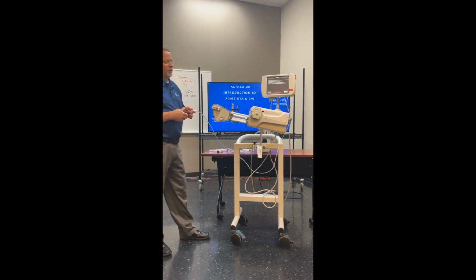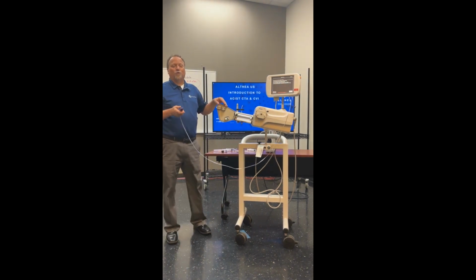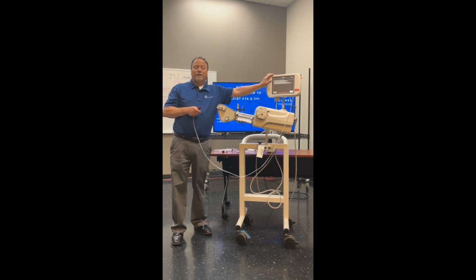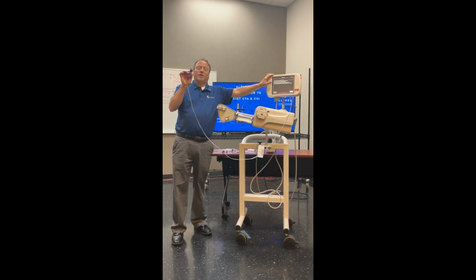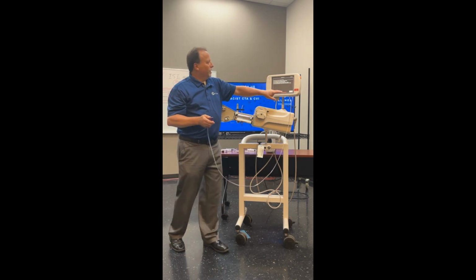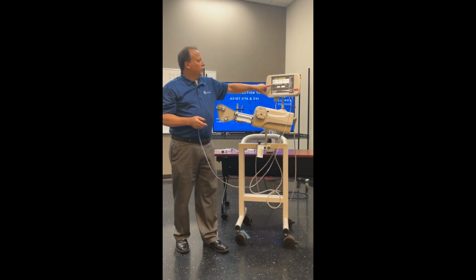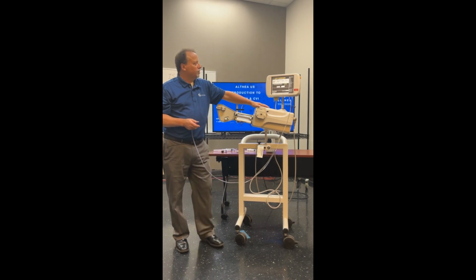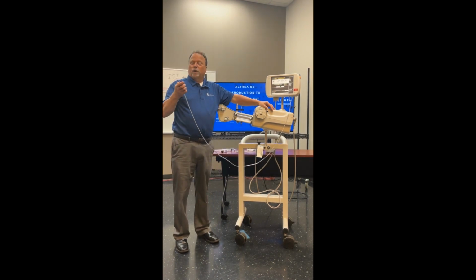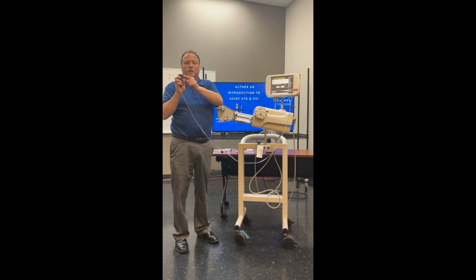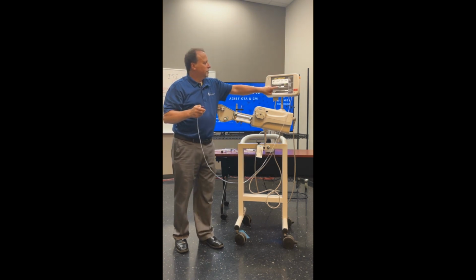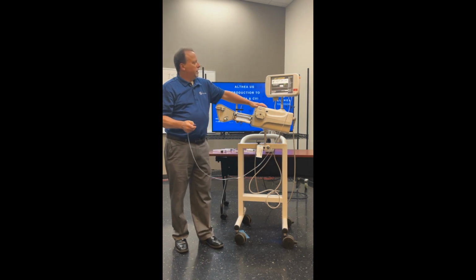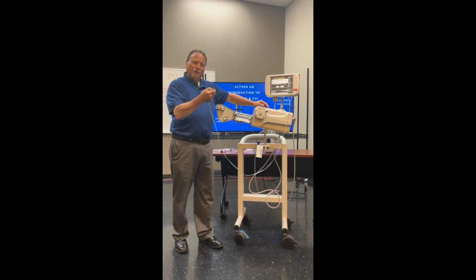Another unique feature on this is how do you control flow? Well, you can program it in, but you also have to calibrate the hand controller. And it's calibrated every time you put a new one on, and this will be good for 5 cases. So we're going to hit done, and where it says starting hand controller calibration, once you hit OK, you have 4 seconds to push down the C button on the hand controller. And that will calibrate the pressure of the operator's thumb.